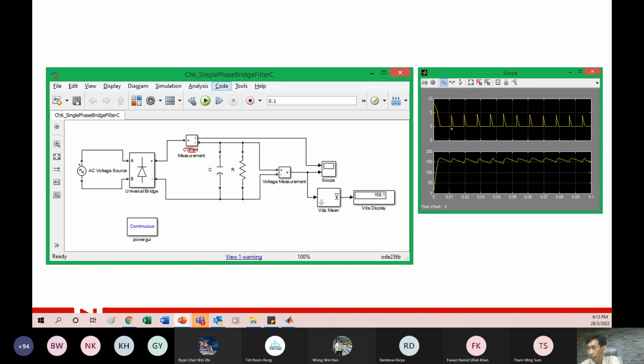Every time they switch on, it charges and draws a lot of current. This is the main culprit that causes harmonics at the grid. A small power supply, like the one used for a phone charger, is okay, the harmonics are so low. So that tells you it does not draw current in a linear form, and that is the main reason it causes harmonics.